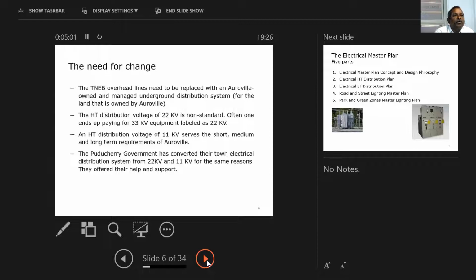The HT distribution voltage of 22 kV is a non-standard voltage, as you know. The standard voltage would be 33 kV, so we always end up buying 33 kV equipment for using it at 22 kV. So obviously the cost of the equipment was very high. The HT distribution voltage of 11 kV will be much lesser in cost, and also the space required for the transformers will be very minimal, and we can manage, and the cost also will be reduced.